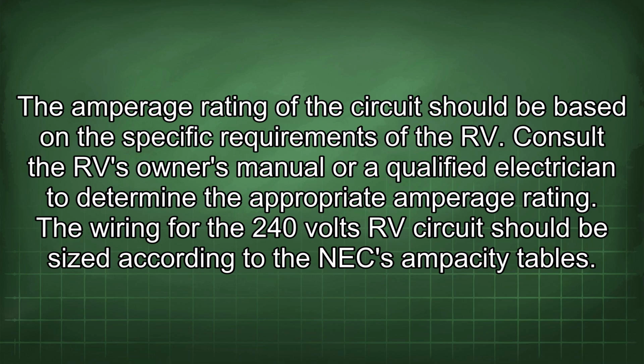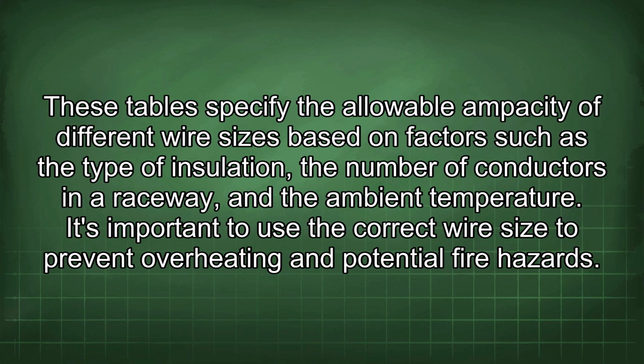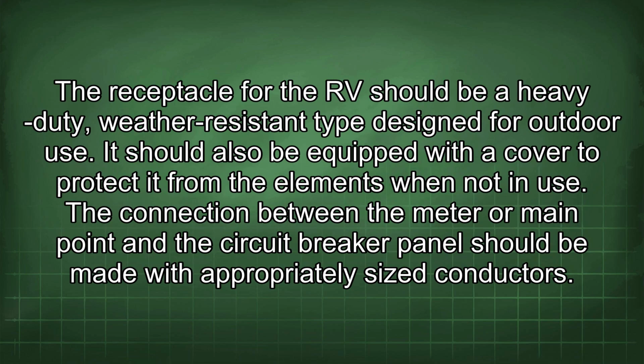The wiring for the 240-volt RV circuit should be sized according to the NEC ampacity tables. These tables specify the allowable ampacity of different wire sizes based on factors such as the type of insulation, the number of conductors in a raceway, and the ambient temperature. It's important to use the correct wire size to prevent overheating and potential fire hazards. The receptacle for the RV should be a heavy-duty, weather-resistant type designed for outdoor use. It should also be equipped with a cover to protect it from the elements when not in use.